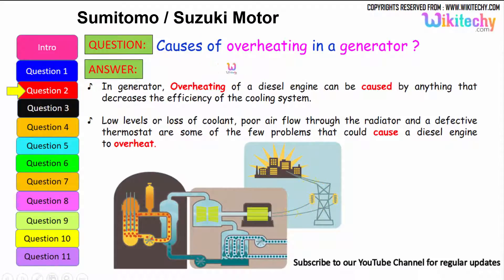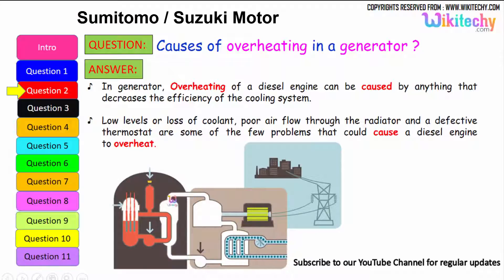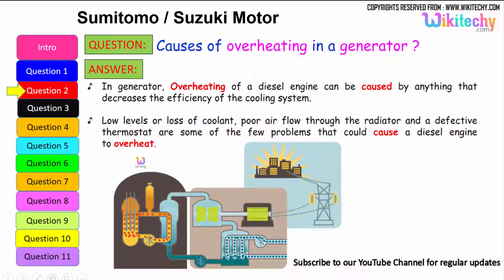Let us move on to the next question: causes of overheating in a generator. In a generator, overheating of a diesel engine can be caused by anything that decreases the efficiency of the cooling system. It can be due to loss of coolant or low coolant levels, poor air flow through the radiators, and a defective thermostat — these are some of the problems that could cause a diesel engine or generator to overheat.